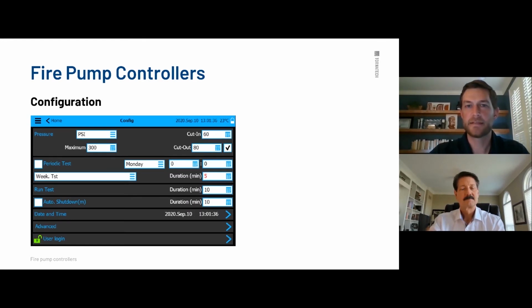This is the gear, the configuration page, like I mentioned when I was showing the drop down. This is where you're going to set your cut in and your cut out pressure. You can see that here at the top. We have cut in and cut out. And just to explain this check mark here next to the cutout, from the factory, we have it set to where the check mark is not there. It's just a gray, or I guess it's a white box, and cutout is grayed out.